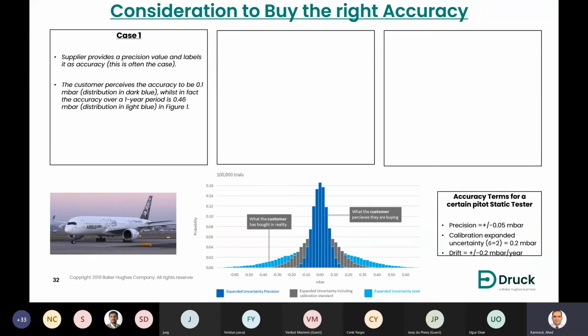Why is that? Because the accuracy term written by the manufacturer includes only the precision as the accuracy. This is wrong; these are 3 types of errors, and you cannot neglect any of them. So this translates to plus or minus 53 feet of uncertainty at 41,000 feet by excluding these 2 terms from the accuracy calculation. You have to remember that precision does not equal accuracy. Precision is just one source of errors. You have other sources of errors which should be taken into consideration when we speak about the total accuracy of the device.